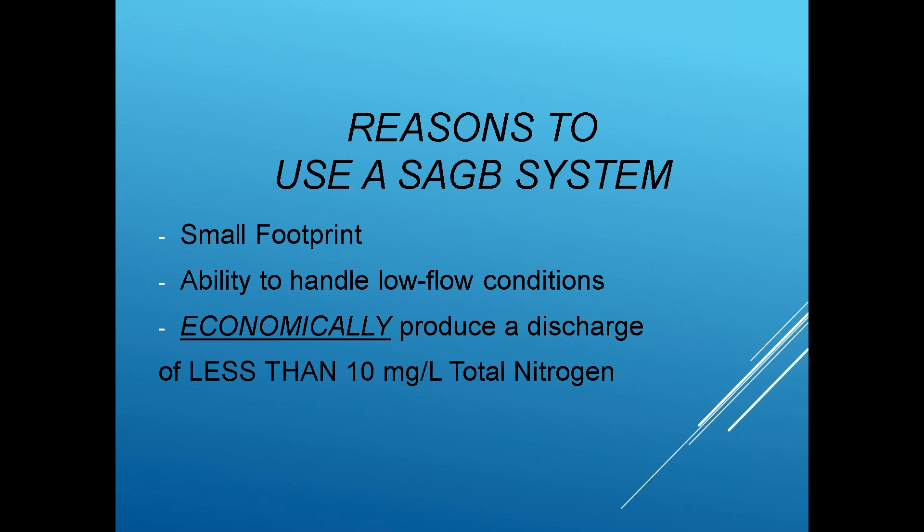There are several reasons to use a SAGBI. One is a small footprint — with 250 square feet per cubic foot of surface area, you have a large surface for your biomass in a compact space. It can handle low flow conditions, making it good for seasonal applications. And it's a really economical way to produce a discharge of less than 10 milligrams per liter of total nitrogen. The system I'm familiar with has a reactor that nitrifies and then a polishing filter that denitrifies, both being SAGBIs.